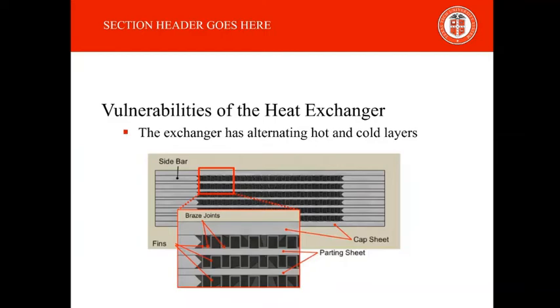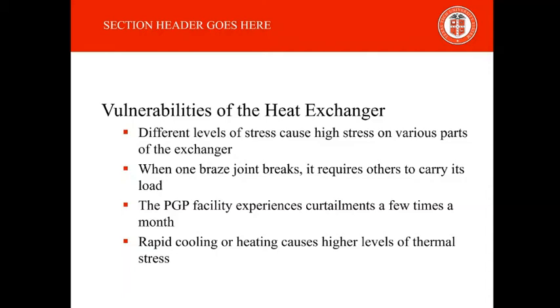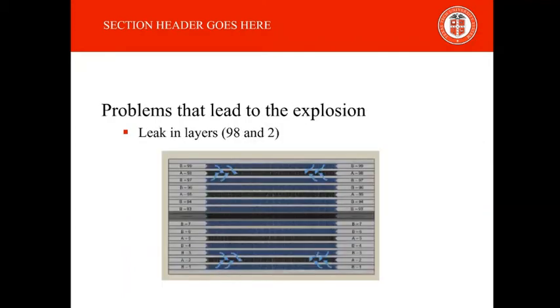However, some of the disadvantages include exposure to fluctuating thermal stresses and plugging of small passages. When a BAHX is exposed to fluctuating thermal stresses over an extended period of time, this can lead to thermal fatigue, which will be one of the main causes of this accident. The post-incident examination of this exchanger revealed very clear service-related thermal fatigue at several locations. The exchanger was already experiencing thermal fatigue in September 2015.